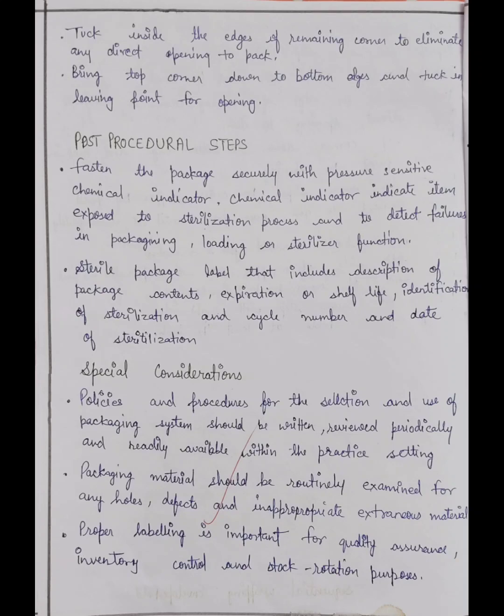For post-procedure steps: fasten the package securely with pressure-sensitive chemical indicator tape. The chemical indicator indicates the item was exposed to the sterilization process and helps detect failure in packaging, loading, and sterilizer function. Label the sterile package to include description of package content, expiration, shelf life, identification of sterilization cycle number, and date of sterilization.